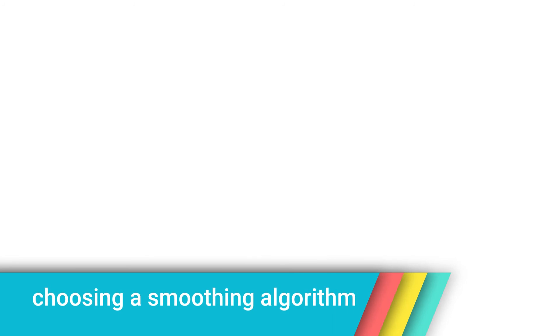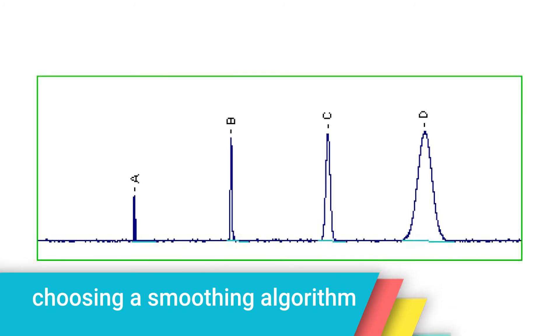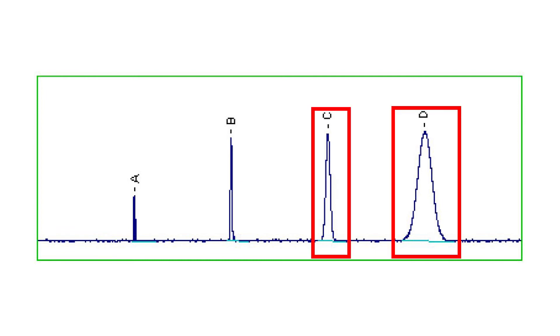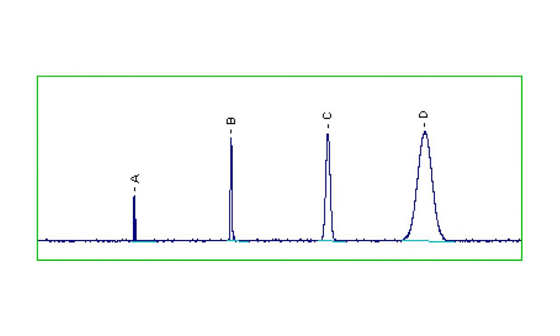Choosing a smoothing algorithm. The previous illustrations all employed the rectangular smoothing algorithm. For peaks that are sufficiently wide, such as the last two peaks above, the other algorithms produce similar results, and there is no particular advantage in choosing one over another. However, when noise levels are high, it may be necessary to use a relatively large value for the smoothing time, and the rectangular smoothing algorithm may cause unacceptable peak distortion. In such situations, the triangular and Hamming, and especially the Savitzky-Golay algorithms are superior.